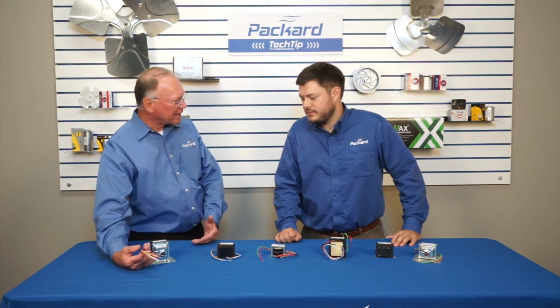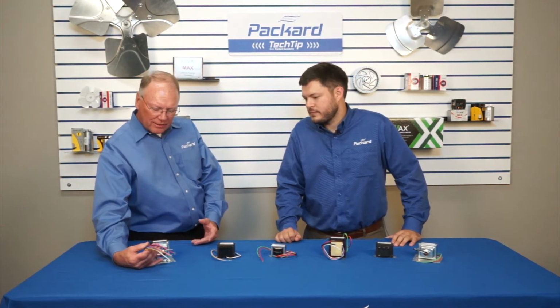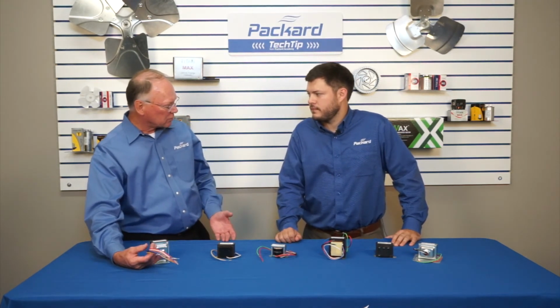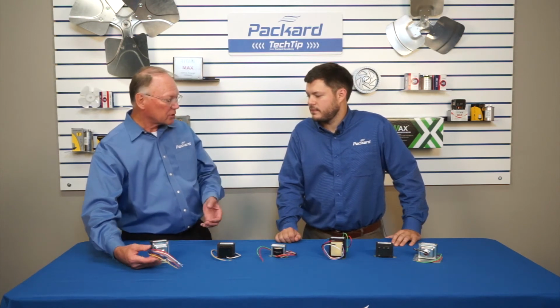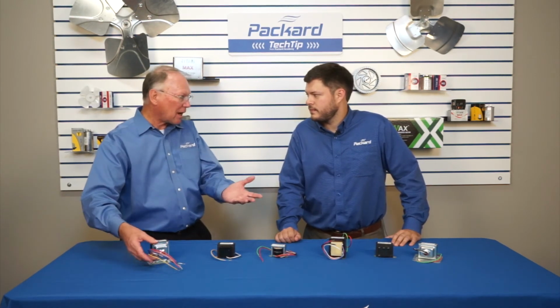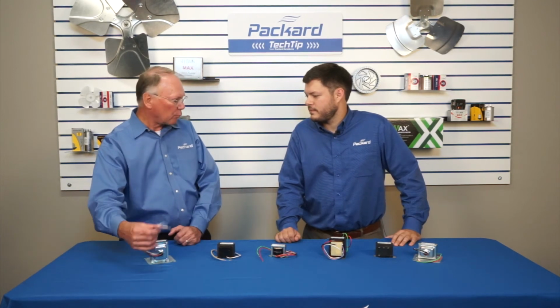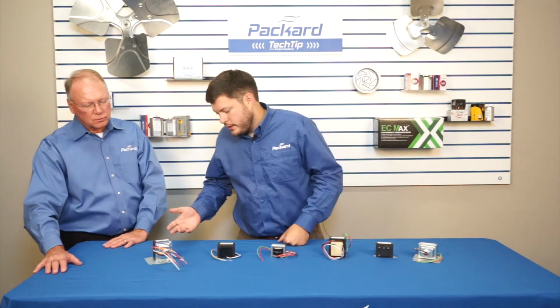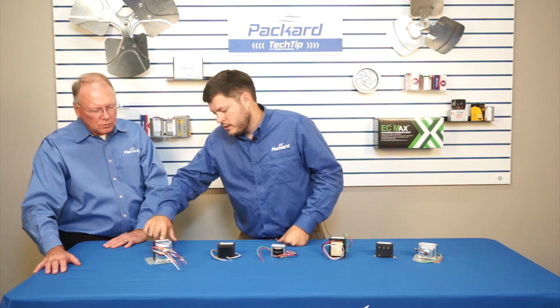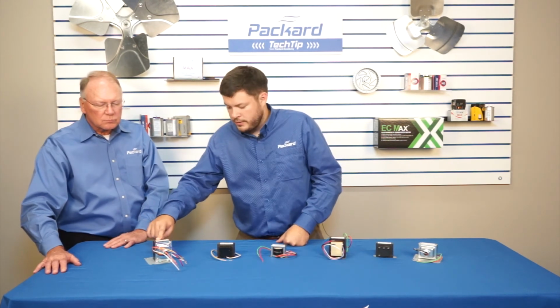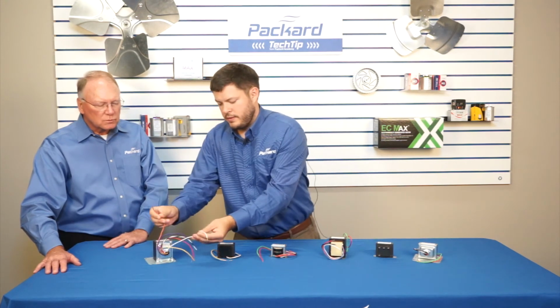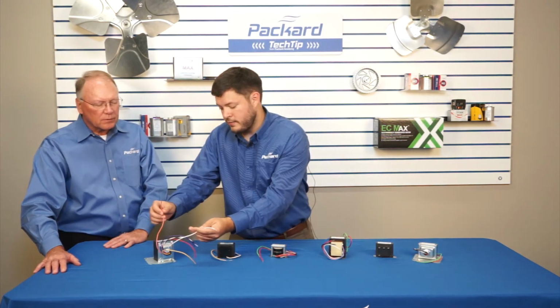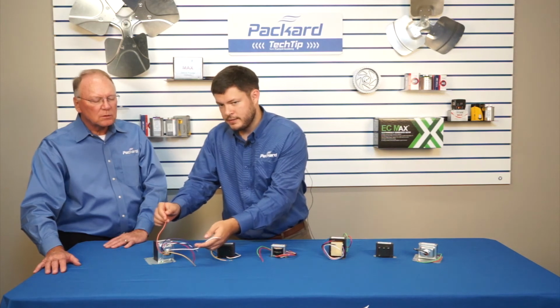Can you show me how I connect these leads, Joey? Let's say that I have an application where my source voltage is 240 volts and I want 120 volts going to a particular product to operate it. How would I select the right wires, and what do I do with all of these wires? So with a 240 volt primary, you're going to need orange and white. White's your common. If you pull the orange and white leads, the rest of them on your primary side need to be insulated.